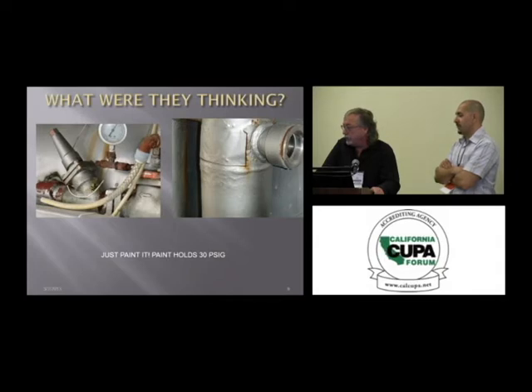Penetrations through walls, ceilings, pipes that change in temperature. In refrigeration, we have certain piping that will be warm at times and cold at other times, such as hot gas defrost reliefs, condensate relief, etc. Those are areas you should pay special attention to. When you have a thermal change, that's typically where the corrosion starts on a system first.